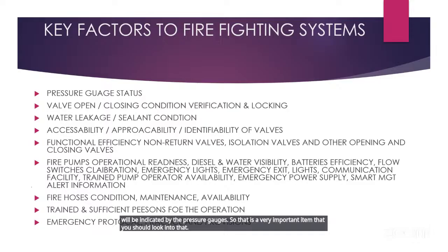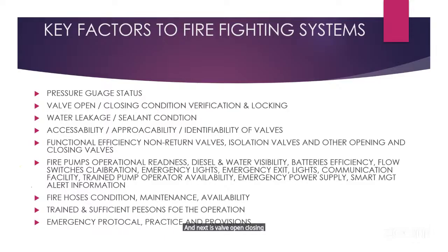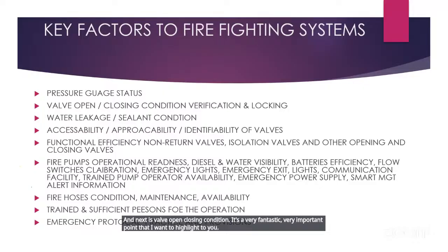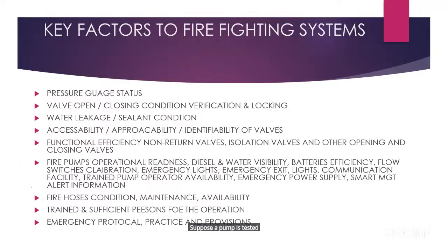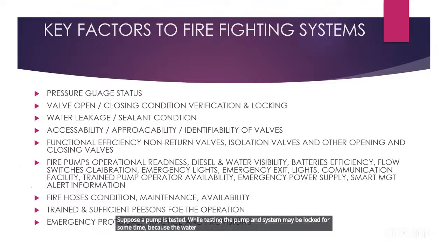And the next is valve open and closing condition. This is a very important point that I want to highlight to you. Suppose the hydrant valve from the pump room is closed in the main section, then the water will not go there. Suppose a pump is tested; while testing the pump, the system may be locked for some time because the water will be going through the tank itself. At that time, when you forget to open the valve, the system will not be supplied by the fire pump.